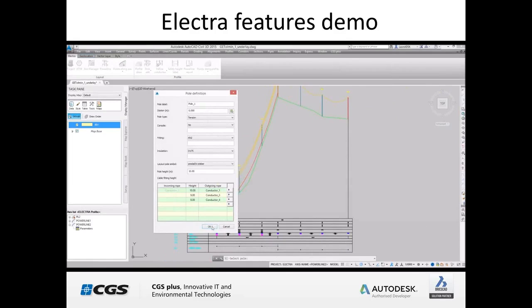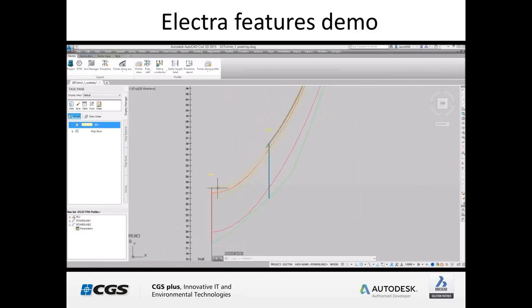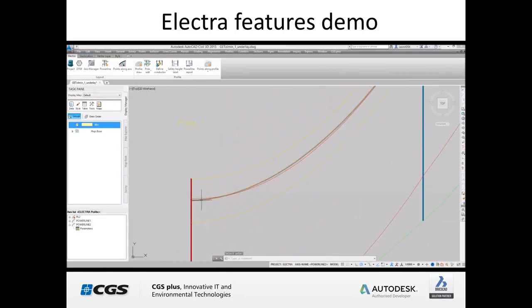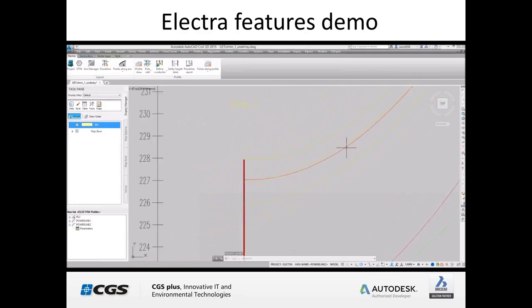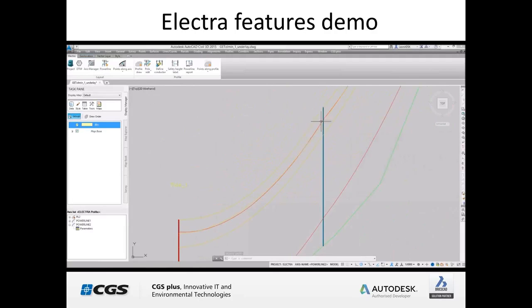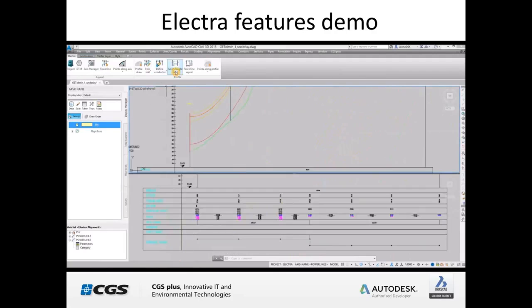And when we go into the drawing, the red line presents that safety height, and we can see here that it interferes with the middle cable. So we have to change something, either physical data of the uppermost cable or lower the middle cable, etc.